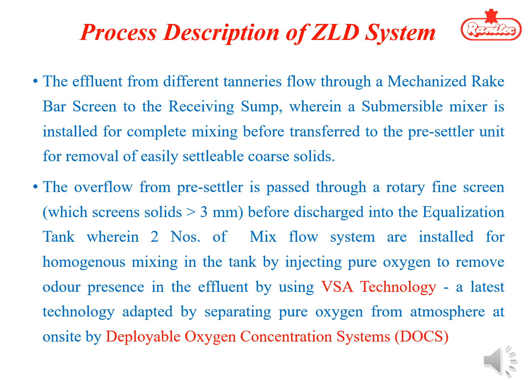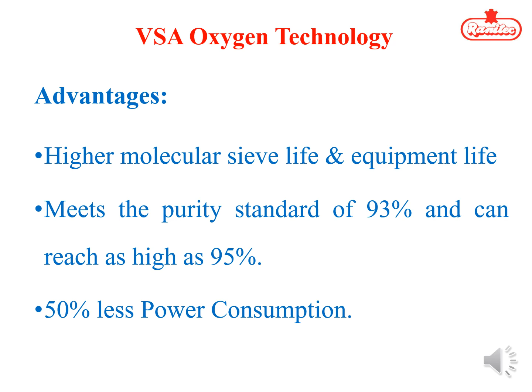The VSA oxygen technology advantages are high molecular sieve life and equipment life, meets the purity standard of 93% and can be reached as high as 95%, and 50% less power consumption than pressure swing adsorption technology. So this is the animation video of the VSA technology. The atmospheric air is taken by the VSA by using the reversible blower. It will be fed to the heat exchanger for removal of the moisture present in the air. Then it is passed through the molecular sieve for separation of the oxygen and nitrogen. So whatever oxygen is separated will be collected in the storage tank, that will be used for the process.